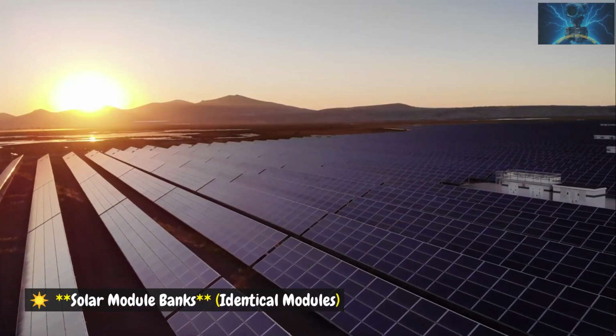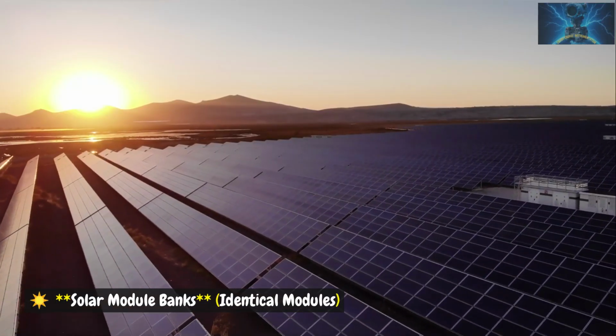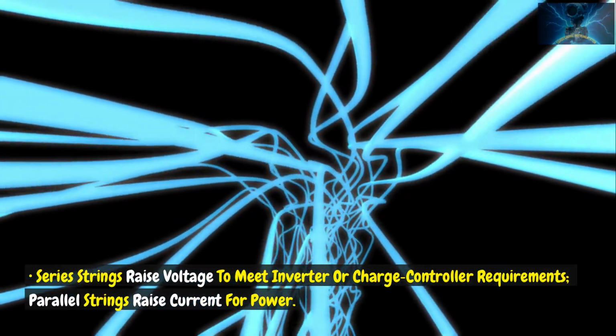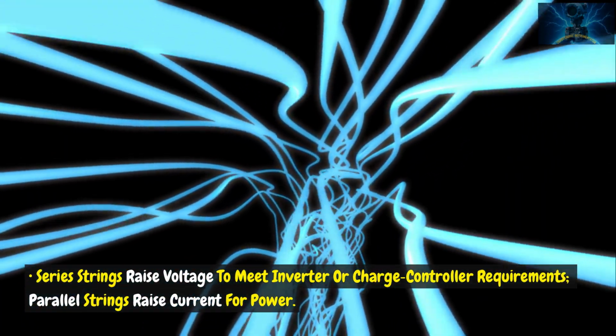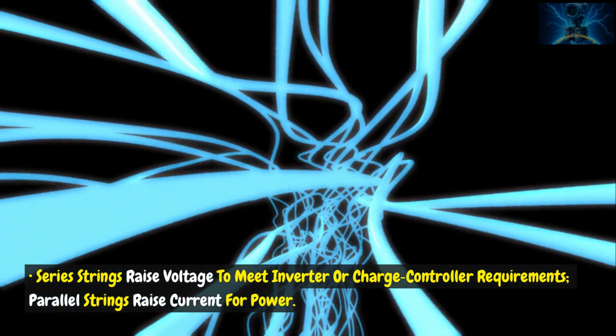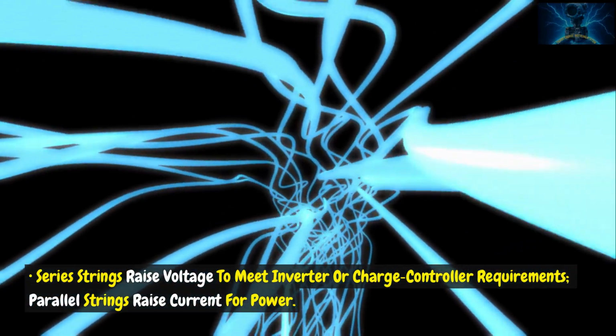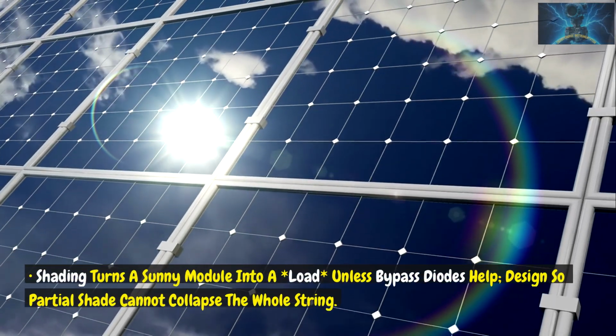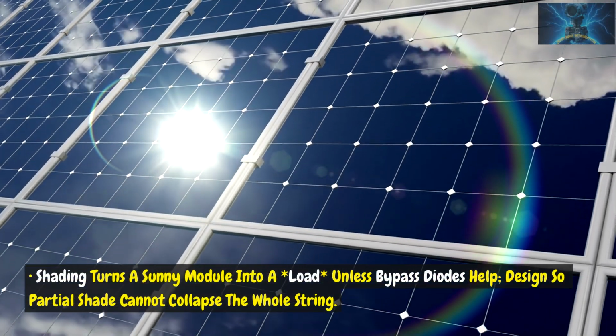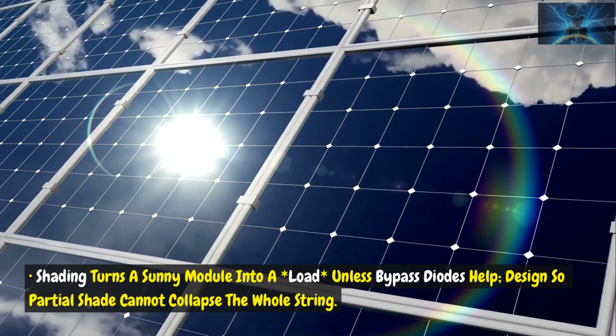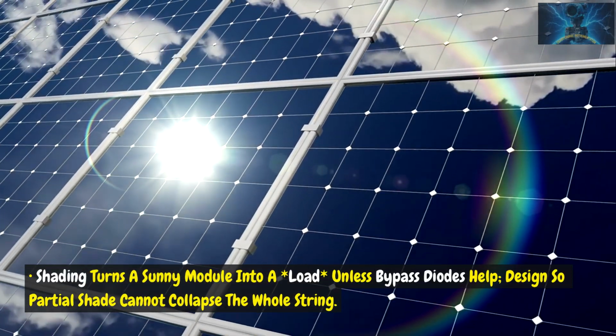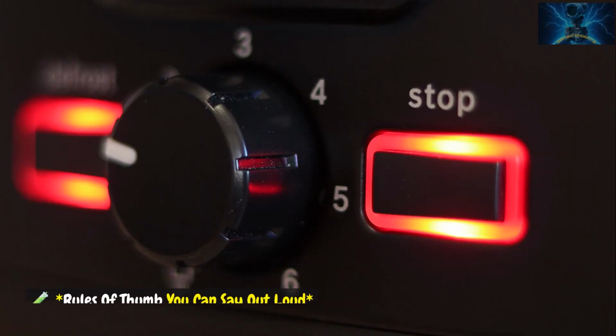Solar module banks, identical modules. Series strings raise voltage to meet inverter or charge controller requirements. Parallel strings raise current for power. And shading turns a sunny module into a load, unless bypass diodes help, designed so partial shade cannot collapse the whole string. Rules of thumb you can say out loud.